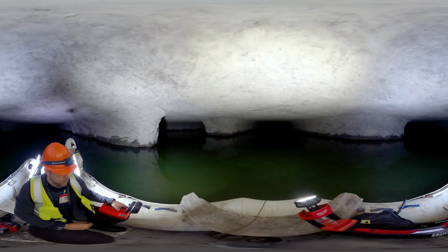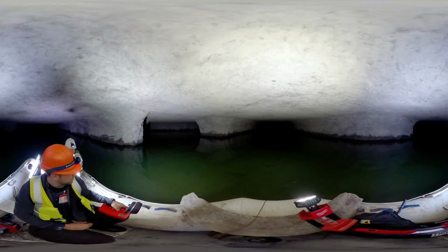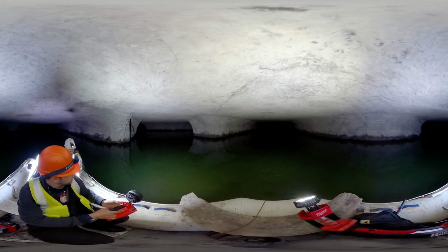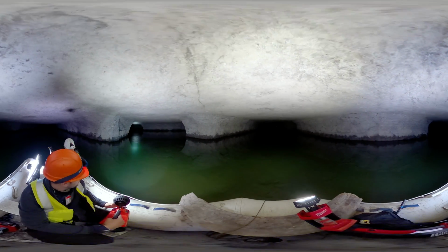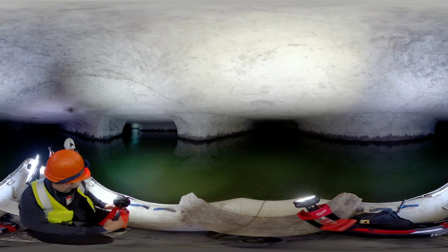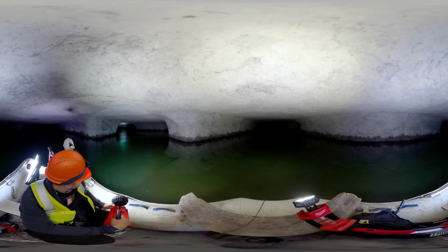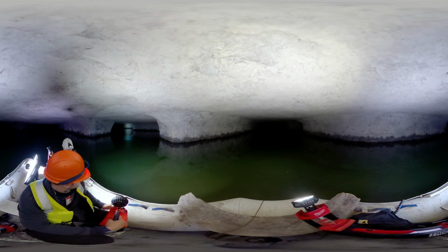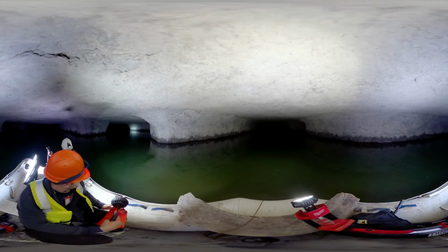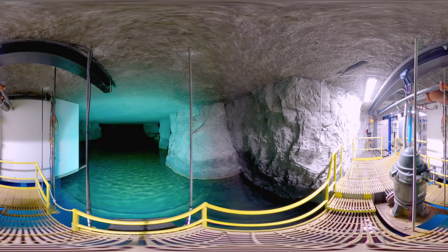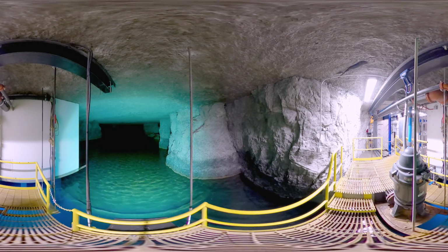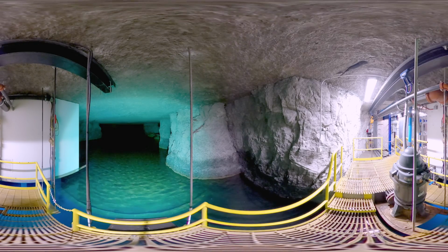Our WPA-1 data center is chilled by a 100-acre underground lake, up to 12 feet deep. The lake is used to cool our facility and is the source for sprinkler systems throughout the facility. Our geo-cooling system consists of 3 redundant pumps which pull the 53-degree water into stainless steel heat exchangers that support a data center chilled water cooling loop.